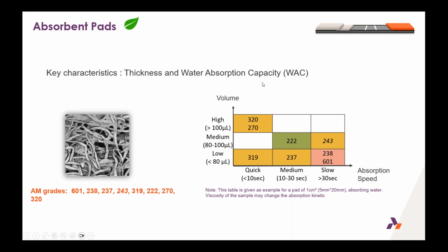Finally, as far as the absorbent pad is concerned, finding the best compromise, mainly in the case of the cassette design, to make sure that it fits the cassette and absorbs enough is the key. Another feature to keep in mind when optimizing the test could be the absorption kinetics. That informs how fast materials absorb. It can help for quick clearance and improving again the performance overall.